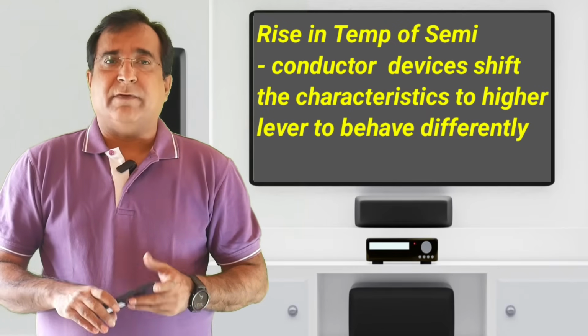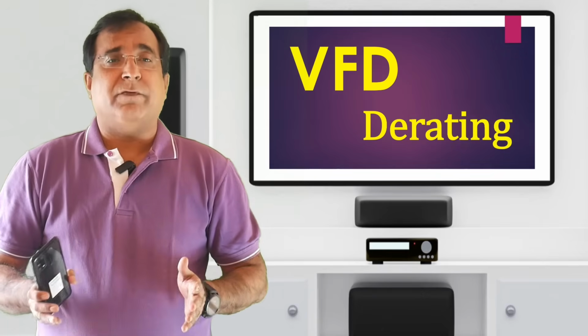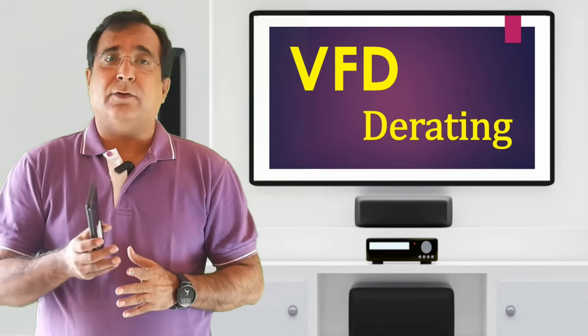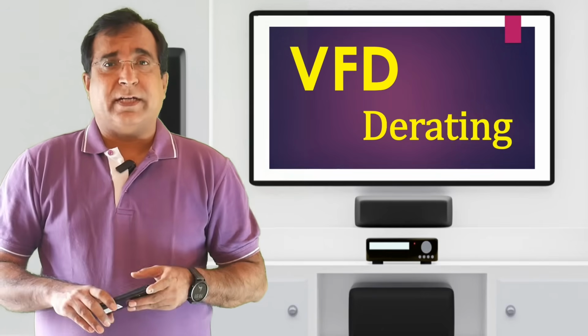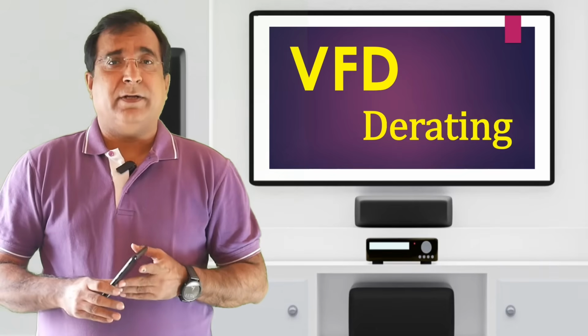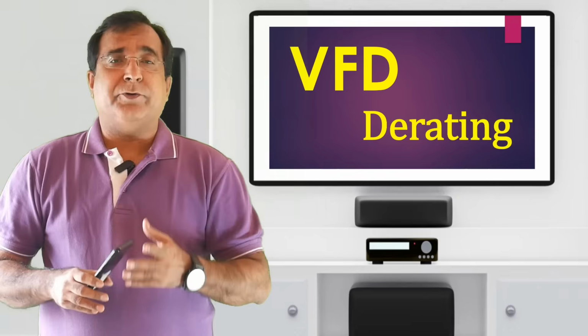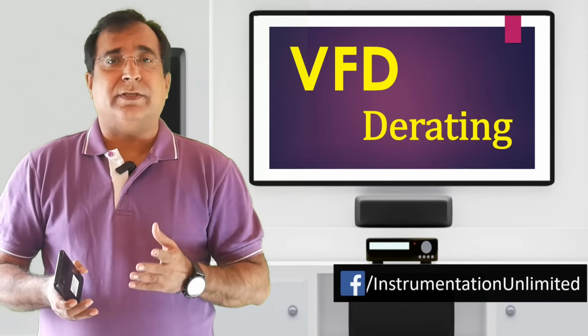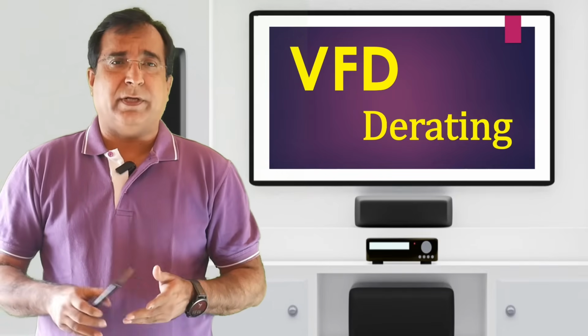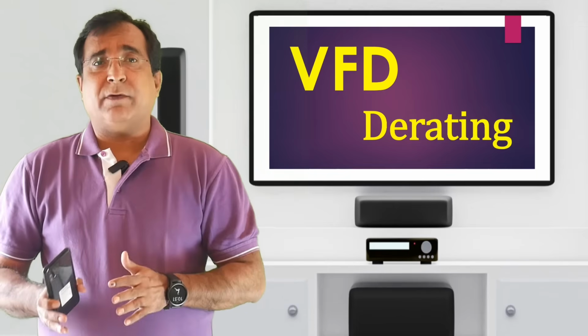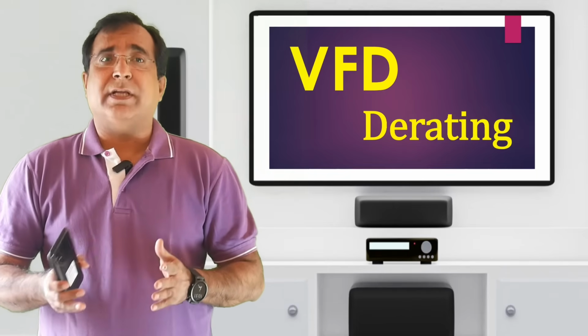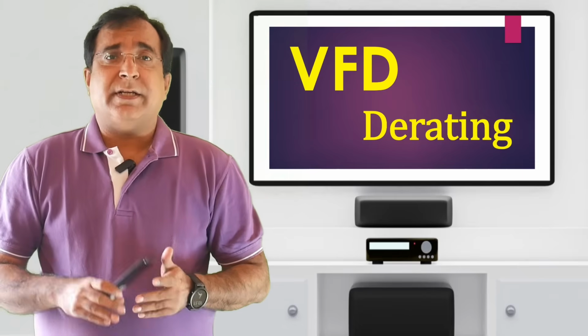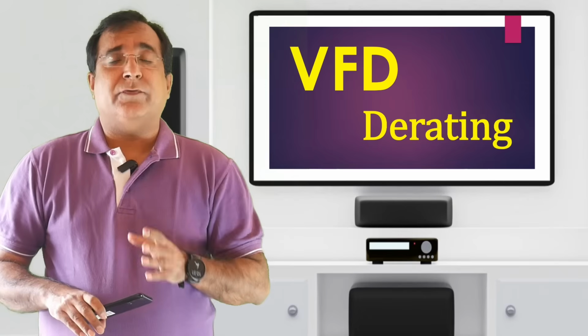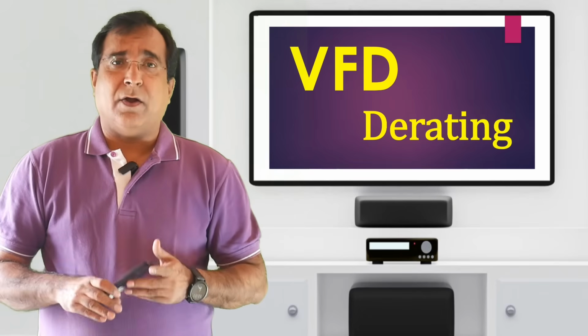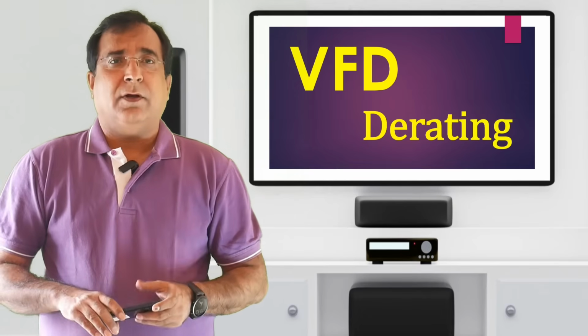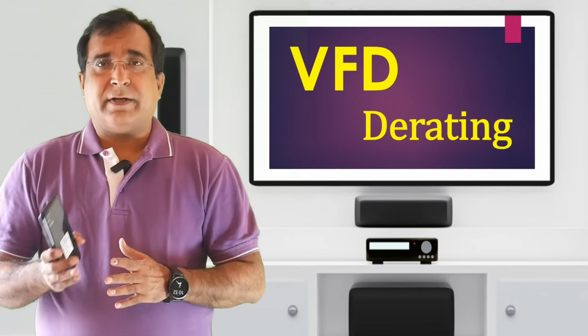You would have observed many times a VFD tripping on an overcurrent fault for no obvious reason, even when it is running at less than the prescribed load. This overcurrent signifies a rise in temperature, which is derating the VFD to trip below normal load. It may be due to altitude, surrounding ambient temperature, switching frequency or continuous duty cycle. The reason will be temperature only. Due to derating, the temperature of the component does not go beyond a limit and cause the component to fail permanently. A rise in temperature causes thermal stress on the component, due to which its material gets degraded and solder joints may get loose.